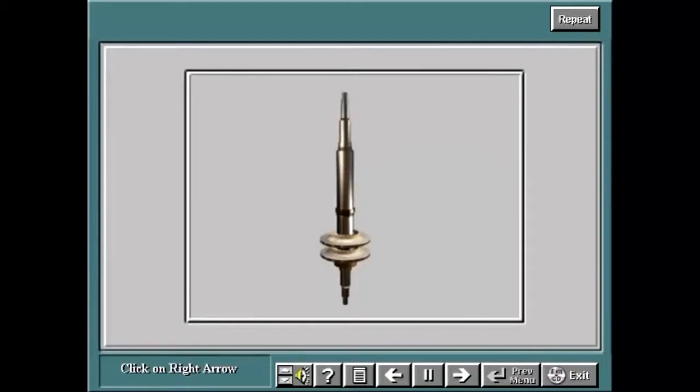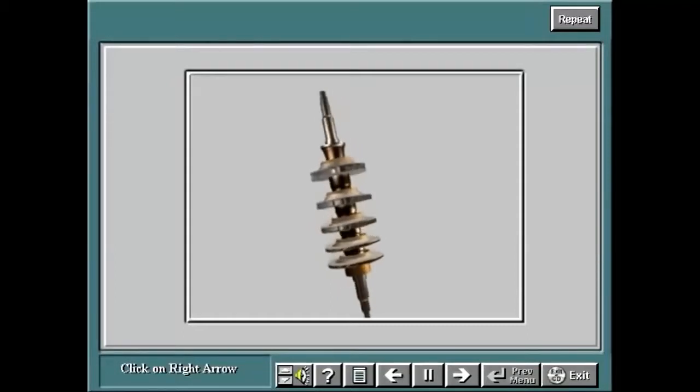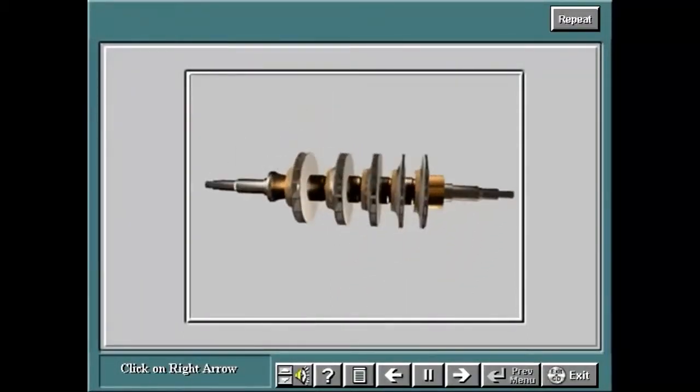The sequence of balancing the rotor, installing the spacer, and adding the impellers is repeated until the suction impeller, spacer, and locking ring are installed and balanced as defined by the customer requirements. Generally, the thrust collar is added last. It is hydraulically expanded and pressed into position on the end of the shaft.